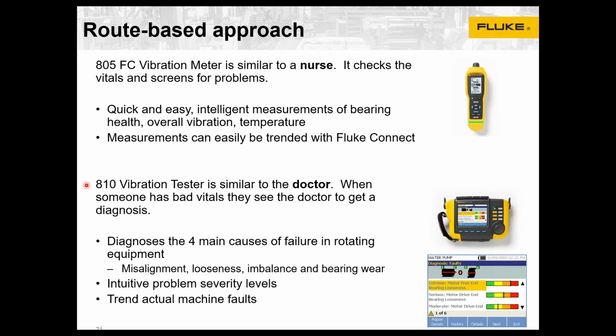On those assets where you find issues, it might be worthwhile to have the doctor visit. So there is a vibration tester, which is more of a drivetrain tester, that not only will tell you you have bearing issues, however, you have that because, for example, as a result of misalignment. So it's more diagnostic, getting to root cause from symptoms. And you can actually trend those faults over time.